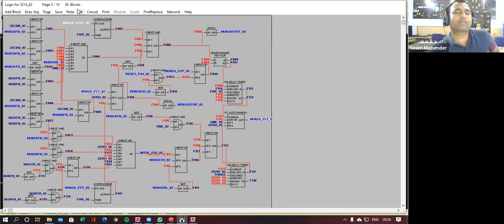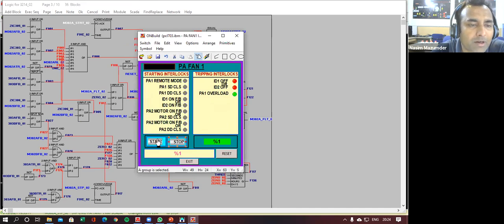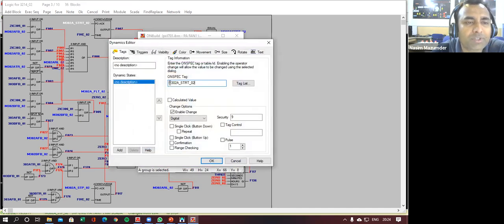So where is this tag coming from? This tag is coming directly from my SCADA, from here, M302A underscore start underscore 02. You see here, M302A underscore start underscore 02. So this will be stored digitally in the memory of your CPU through, say, the TCP/IP protocol. This signal is communicating between your PLC and SCADA, not between your PLC and your field.